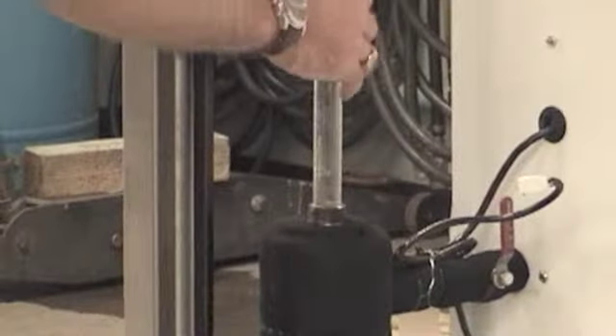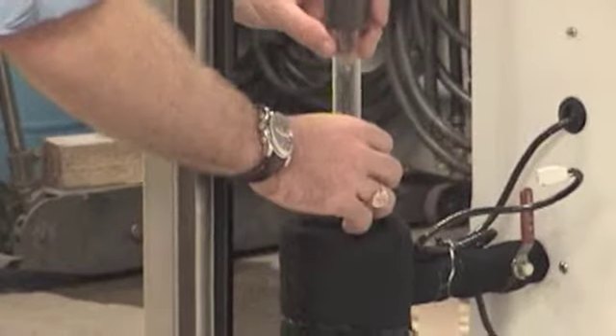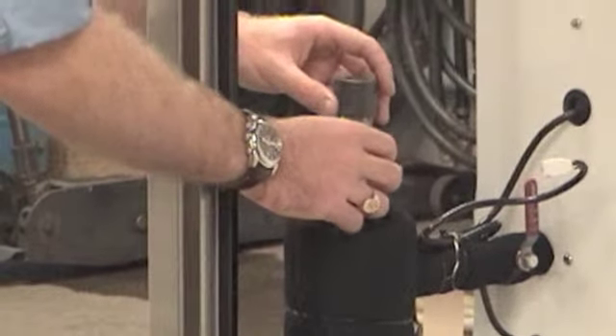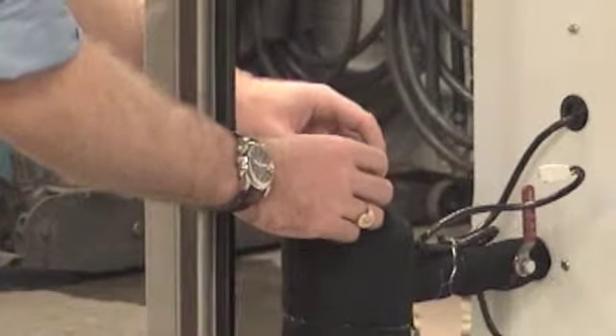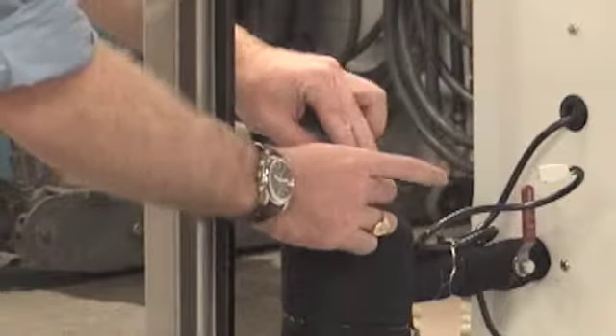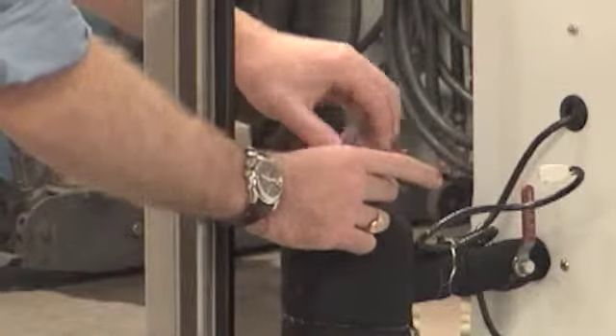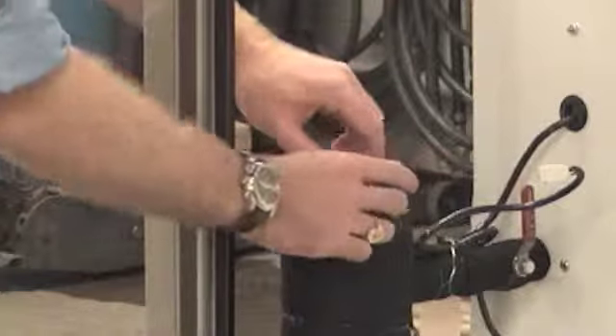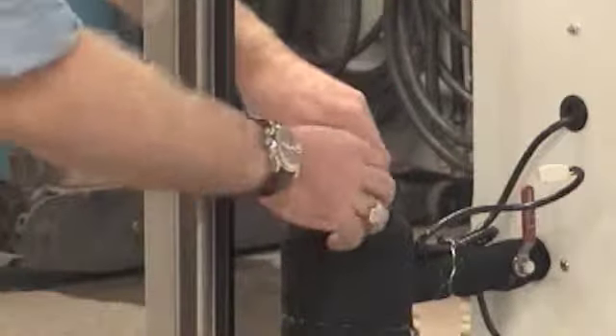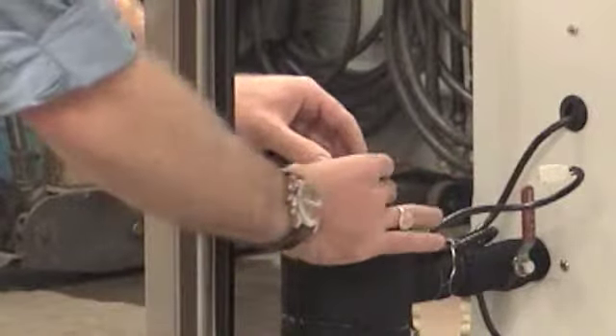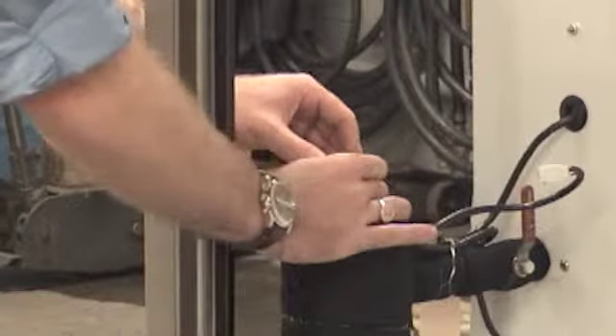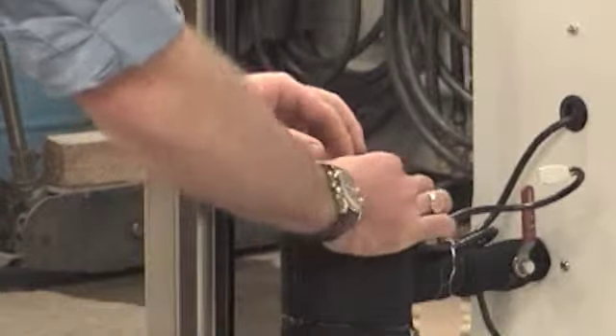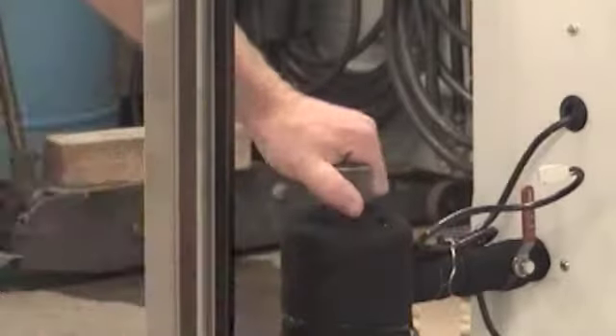This you can put into the sterilizer housing. You want to be very careful. The quartz sleeve is actually very brittle, and you don't want to break it inside of the housing. Screwing that on, again, hand tight, just creating a good seal there is sufficient. You don't need to wrench on it.